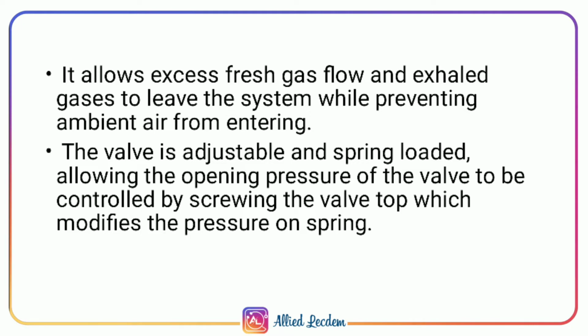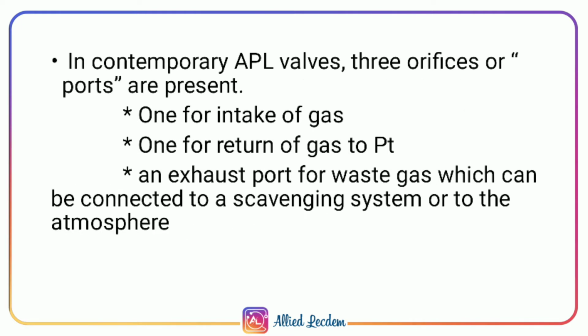The valve is actually spring loaded. So when you turn the cap or the valve top, it controls or modifies the pressure on the spring. The major function of APL valve is actually carried by the spring. The APL valve has 3 orifices which control the flow of gases.